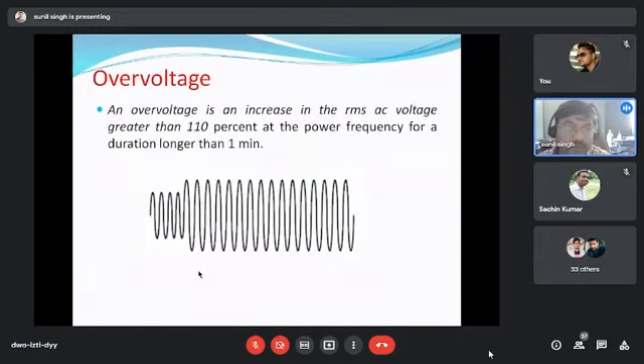Now come to the over voltage. Over voltage and under voltage are very well known phenomena, and we know these two phenomena very well. Over voltage is an increase in the RMS value. Keep in mind, it is the RMS value, not the peak value. An RMS AC voltage greater than 1.1 per unit, or 110% of the nominal, at the power frequency, for a duration greater than 1 minute.